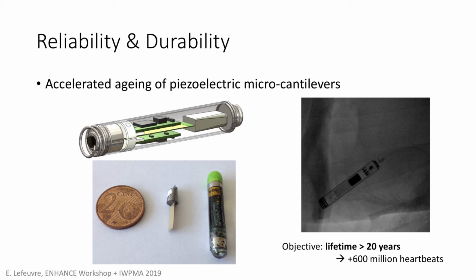Let's say you consider 3 oscillations, 4 oscillations, 5. It depends on the way you extract the energy from the cantilever. If you can extract the energy very efficiently, you will have only a few oscillations, 2 or 3, 4. But if you can't extract the energy very efficiently, you will have a lot of oscillations after each heartbeat. And this will increase the aging of the system.